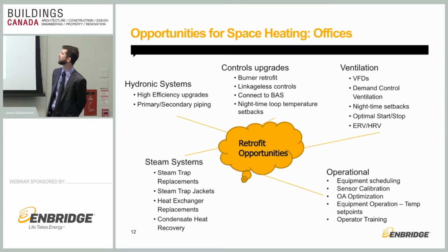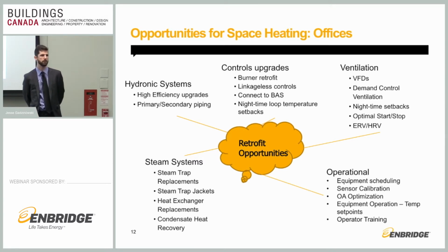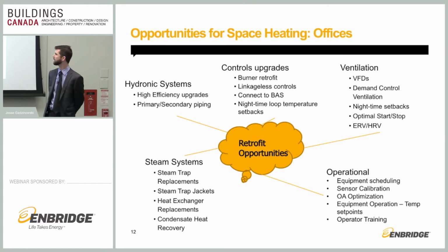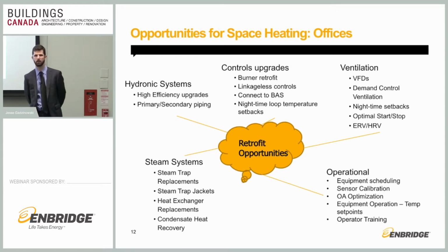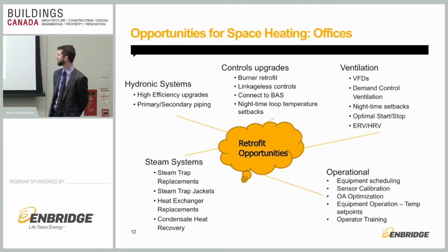And then the operational side, outside of the capital retrofit, just tweaking your building on the operations side to get it performing better. Scheduling your equipment, doing sensor calibration, say your CO2 sensors need to be calibrated or your pressure sensors in your ducts need to be calibrated, things like that, so that the air is being supplied as you would expect. Outdoor air optimization, equipment operation and temperature set points, making sure you can get your set points where you need them, that they're not drifting, making sure that the building's operating appropriately. And then we can do all those things, bring in an engineering company to do all those things for you. But at the end of the day, we would also need the operators to understand the changes. So we provide help for operator training as well. Next, please, Zig.